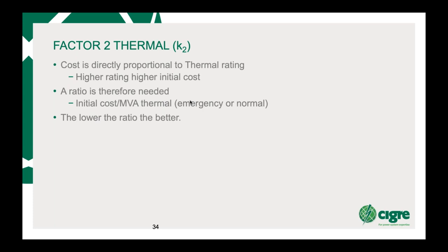So the cost is directly proportional to the thermal rating. Higher the rating, higher the initial cost. So therefore, we're looking at a ratio. Say you take a ratio of the initial cost to MVA thermal. So if you've got a very high thermal rating and a very low initial cost, maybe you've got a good line. So maybe the lower the ratio, the better.